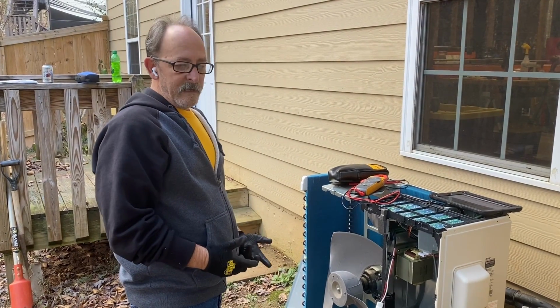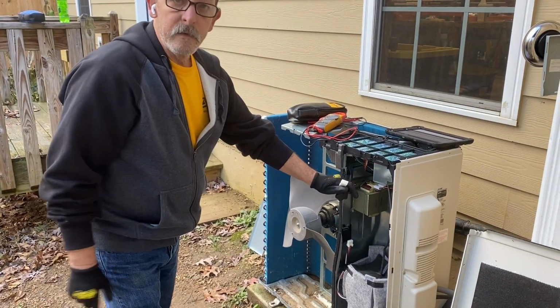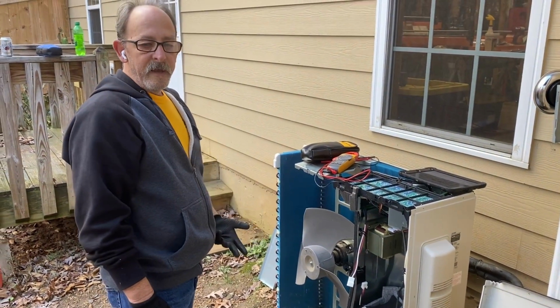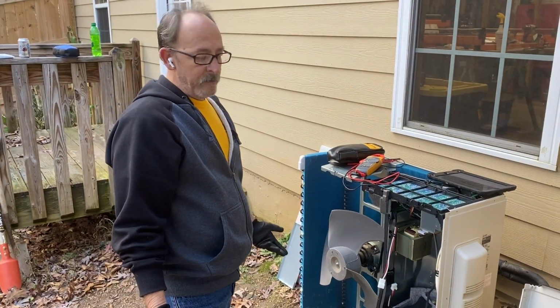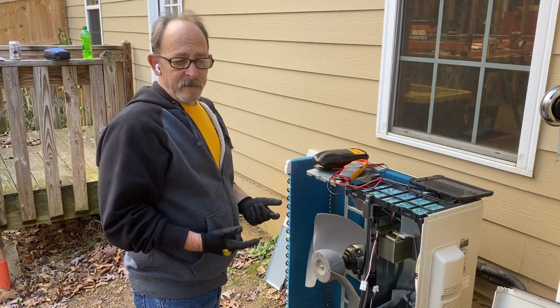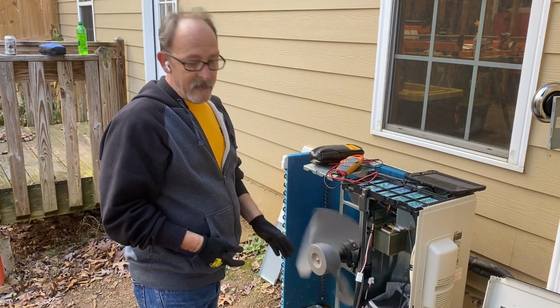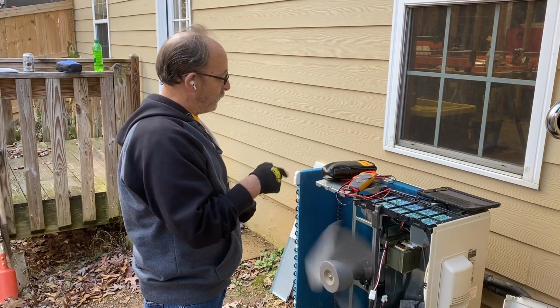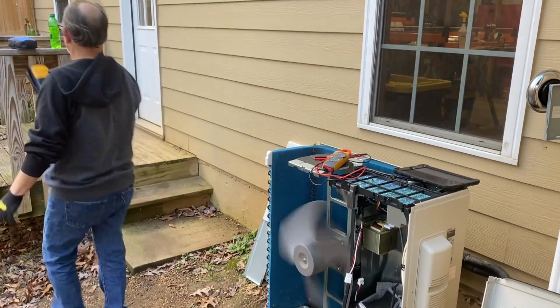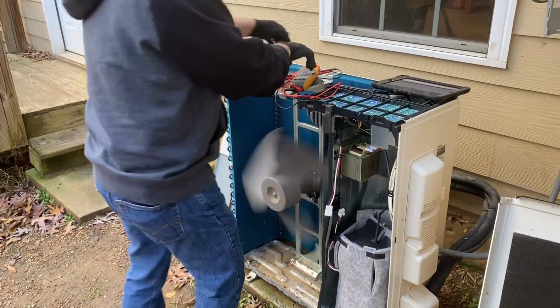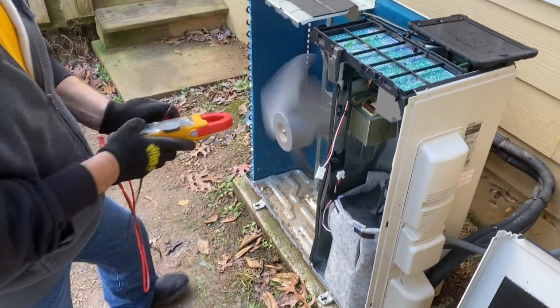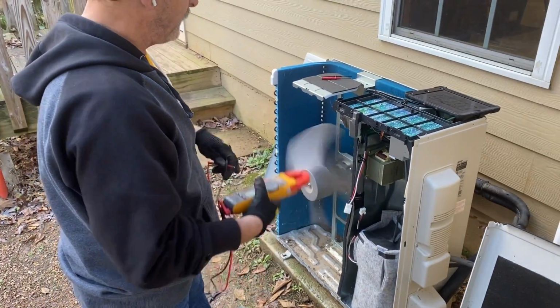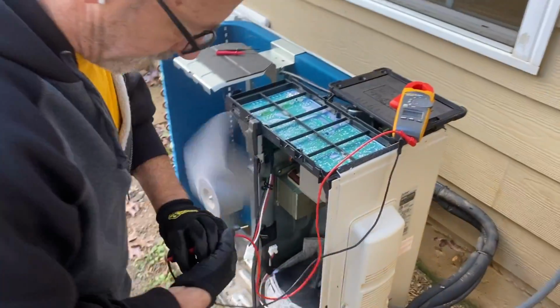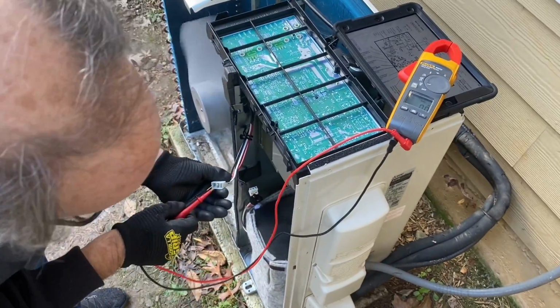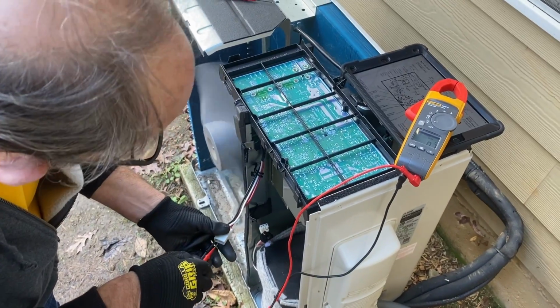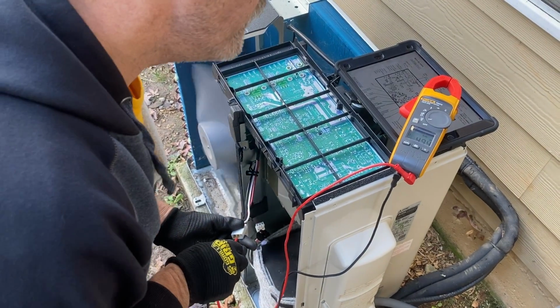And then once it runs that long, I'm going to go ahead and take voltage on these terminals here. Because our compressor is a 3-phase compressor. So all I'm doing is testing balanced voltage. If the voltage is balanced, that tells me the board is good. If the voltage isn't balanced, that tells me there's something going on with the actual board. So, let me go ahead and move this. So that's an AC compressor, so I'm going to put my meter on AC volts there. Then I'm gonna go right here, and I'm gonna just go in between each terminal. So black to red or black to white, and I have 49 volts.